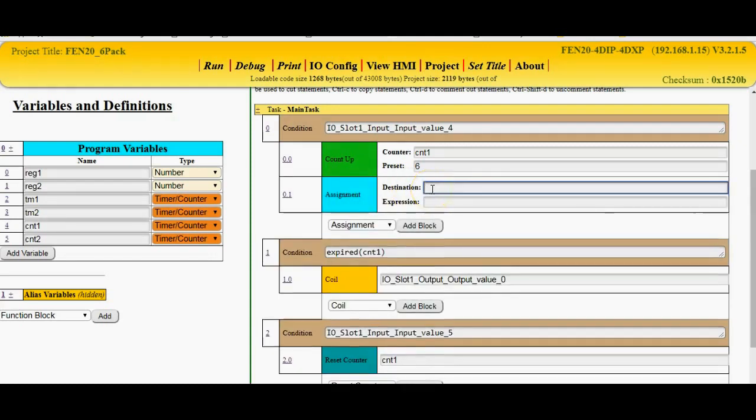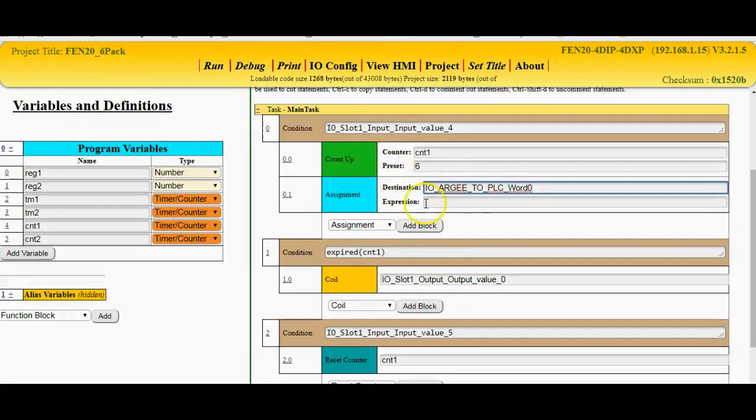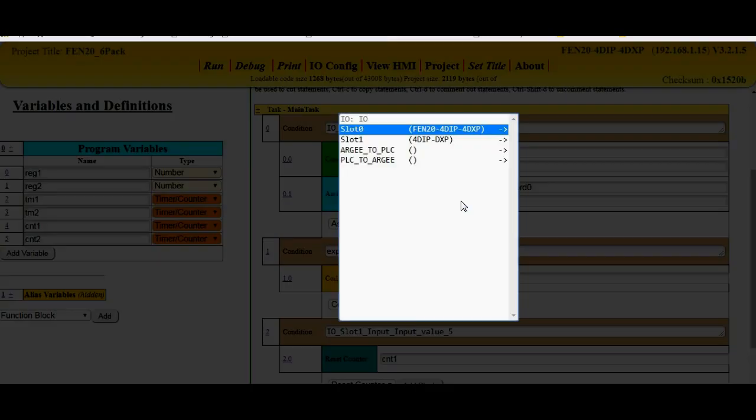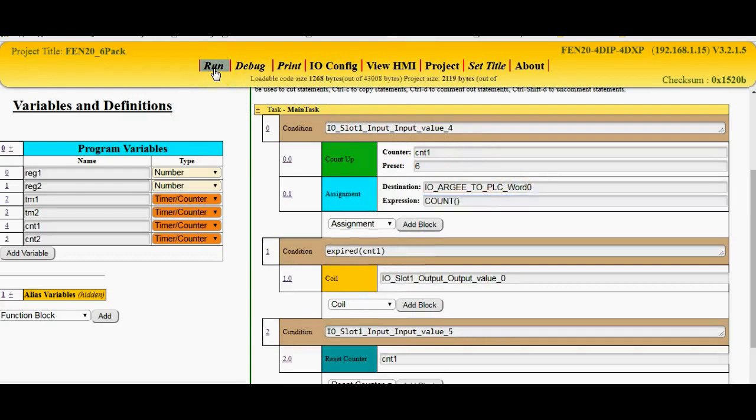And my destination here is going to be a PLC register. So let me hit the Control-I function here, and I want to go ARGEE to PLC. I want to send something out to an HMI to see, so I'm going to choose ARGEE to PLC word zero, OK? And then the expression here that I want to do is the current count value. So let's see here if I can get this to Control-F, counter, and we're going to click here. We're going to show the current count, returns the current count right here. So that should put into the first register going out the value. So let's see here, I'm going to go ahead and hit run here.